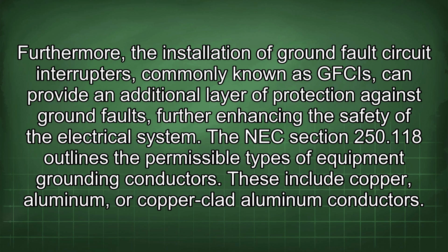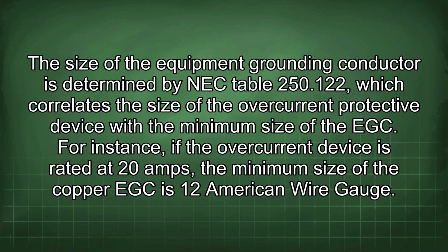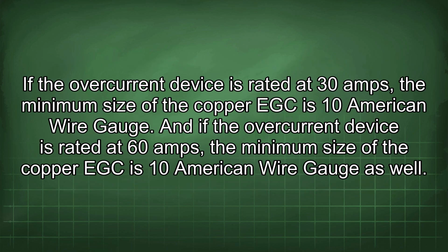The NEC section 250.118 outlines the permissible types of equipment grounding conductors. These include copper, aluminum, or copper-clad aluminum conductors. The size of the equipment grounding conductor is determined by NEC table 250.122, which correlates the size of the overcurrent protective device with the minimum size of the EGC. For instance, if the overcurrent device is rated at 20 amps, the minimum size of the copper EGC is 12 American wire gauge. If the overcurrent device is rated at 30 amps, the minimum size of the copper EGC is 10 American wire gauge. And if the overcurrent device is rated at 60 amps, the minimum size of the copper EGC is 10 American wire gauge as well.